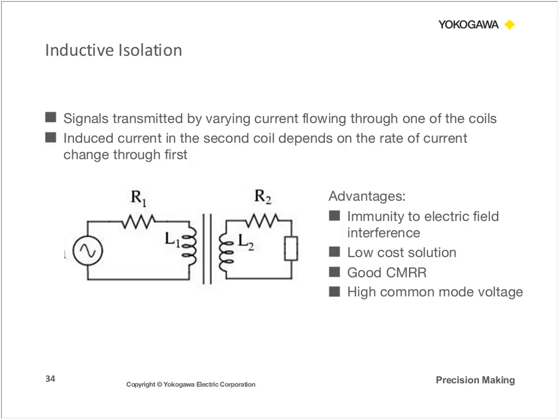Inductive isolation is also good for high-speed transmissions if you're dealing with 100 kilohertz or higher. But the main thing to be careful of is that because it uses a magnetic field for data transmission, you can experience interference from devices that produce an external magnetic field. The other great thing about inductive isolators is that they provide high CMRR performance, and can sustain themselves in the presence of high common mode voltage.